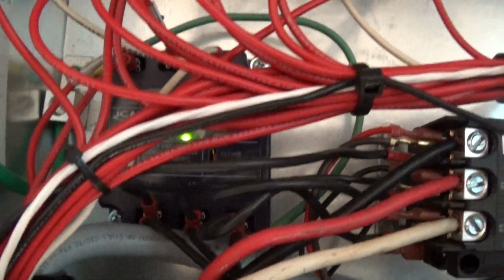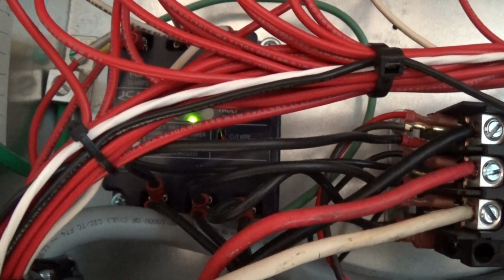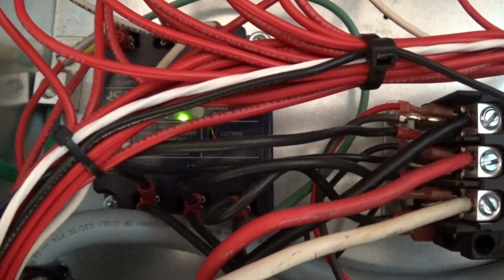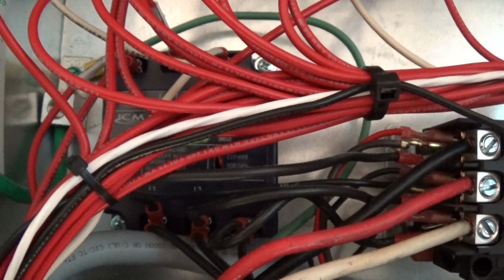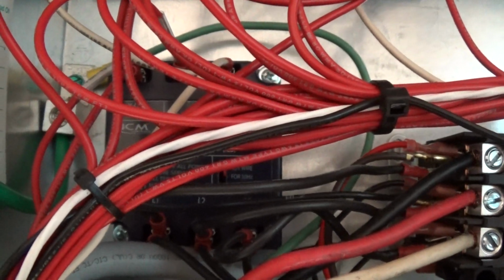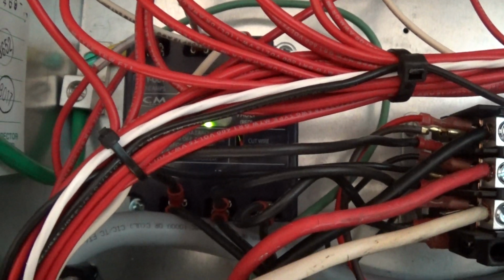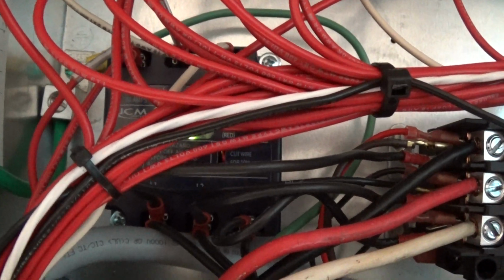And down below here, you see the green light there. That's our PLR, labeled PLR. That's our phase loss reversal monitor. So that's another feature we install in there. That cuts the control voltage out to the chiller in the event of phase reversal, power loss, or if there's a 10% or greater differential between any of the two voltage legs.